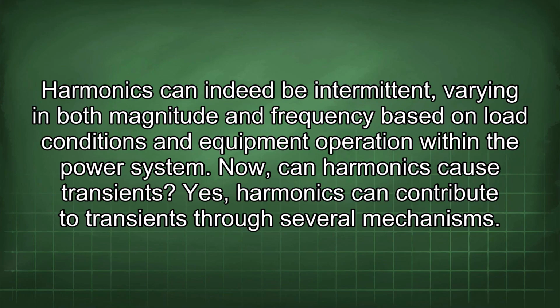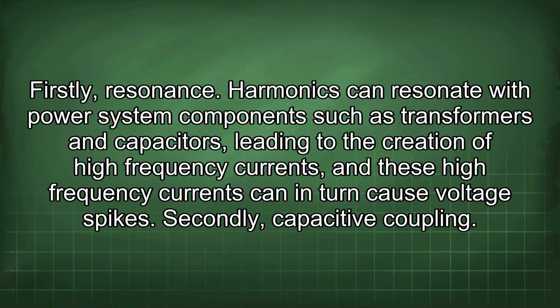Harmonics can indeed be intermittent, varying in both magnitude and frequency based on load conditions and equipment operation within the power system. Now, can harmonics cause transients? Yes, harmonics can contribute to transients through several mechanisms. Firstly, resonance. Harmonics can resonate with power system components such as transformers and capacitors, leading to the creation of high-frequency currents, and these high-frequency currents can in turn cause voltage spikes.